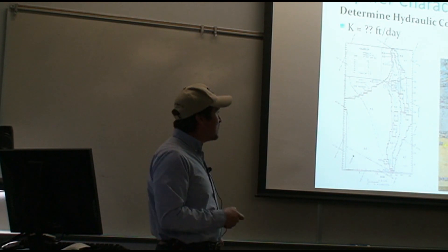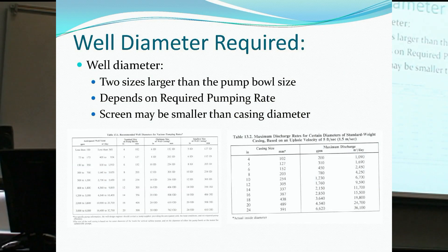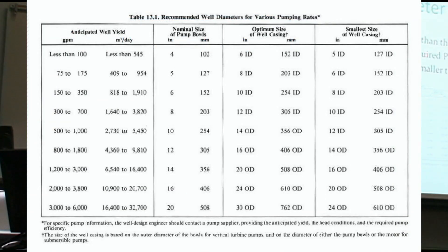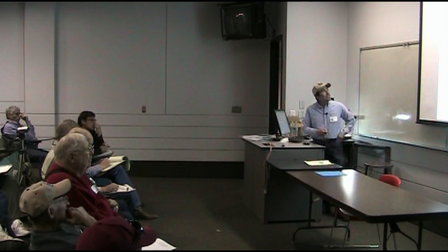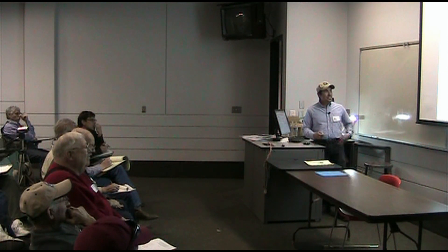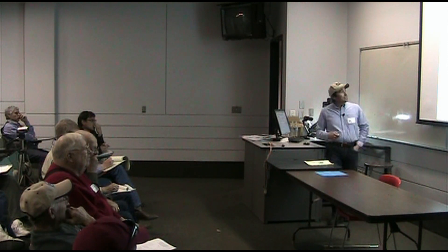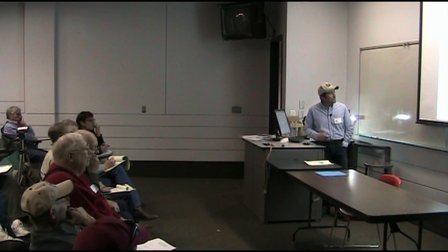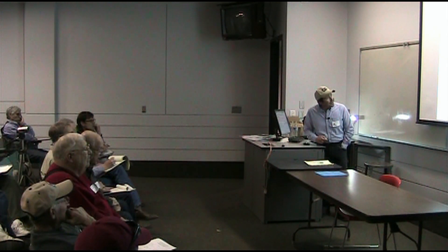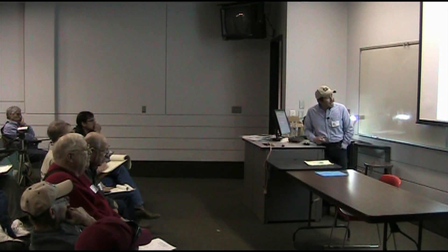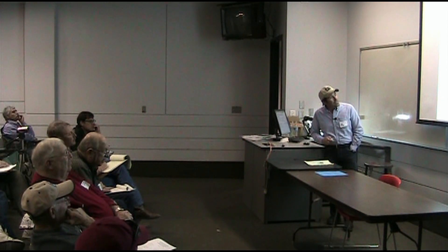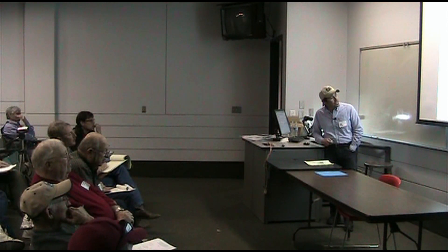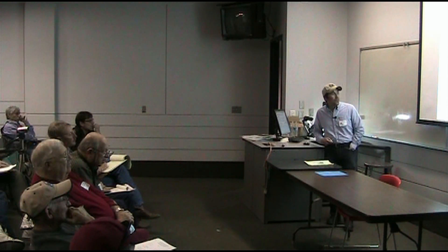As Dr. Samani mentioned, the well needs to be two inches larger than the size of the pump, and this will depend on the desired pumping rate. A small flow pump will be smaller in diameter versus a higher volume well with a bigger pump. For example, for 2,000 gallons per minute, the optimum size would be 20 inch but the minimum would be 16 inch — which is what you most commonly see here in the valley. For a 16-inch well, the maximum recommended discharge rate would be 2,850 gallons per minute.